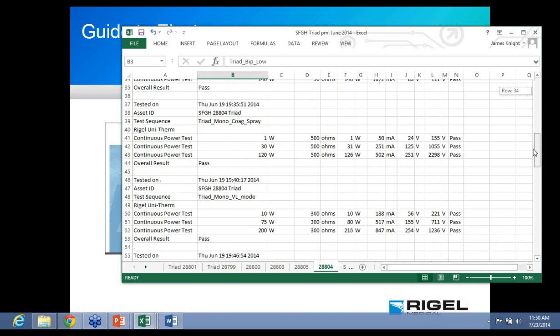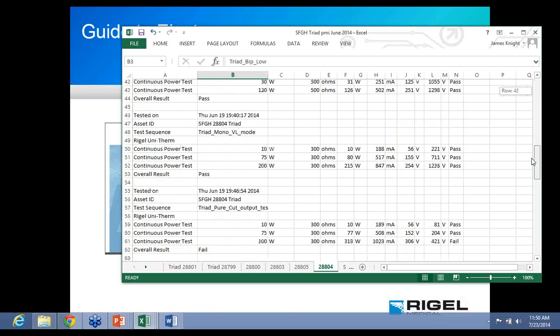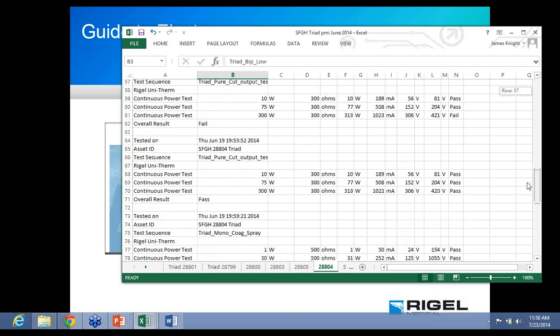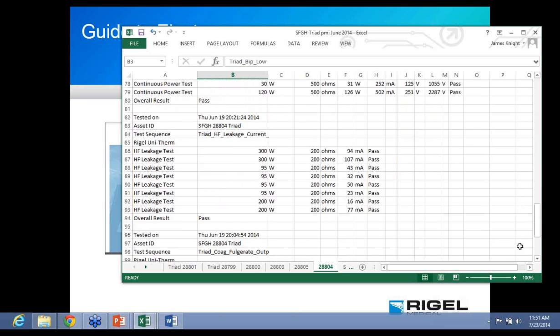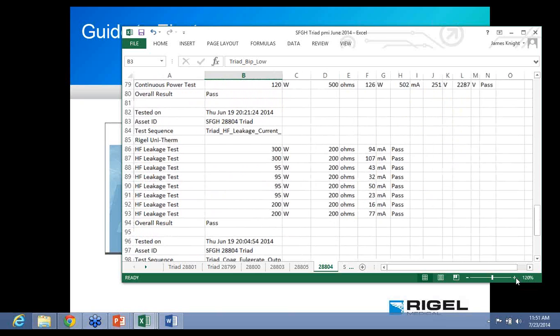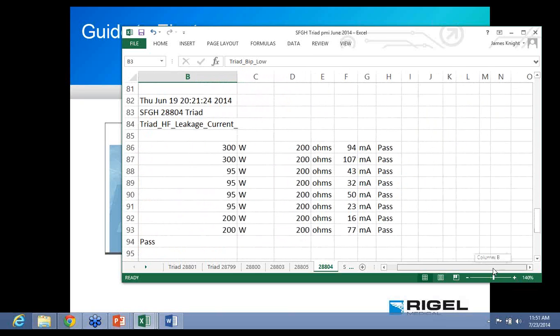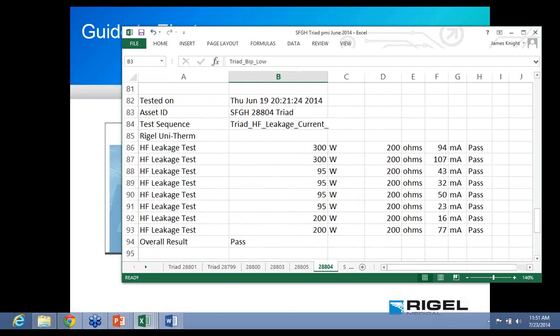Then you have to test the coag, the Valleylab mode, Triad, the pure cut, the monopolar, the HF leakage. There's the HF leakage. Let's zoom in on that. These are the results. So the Triad leakage.